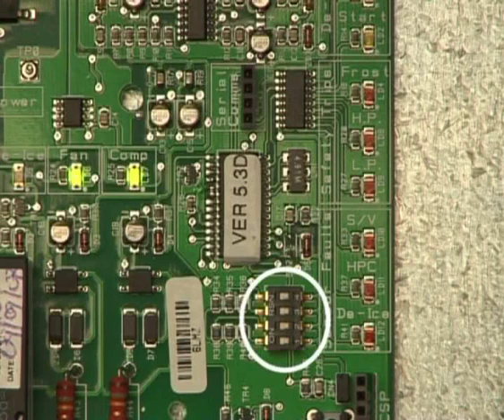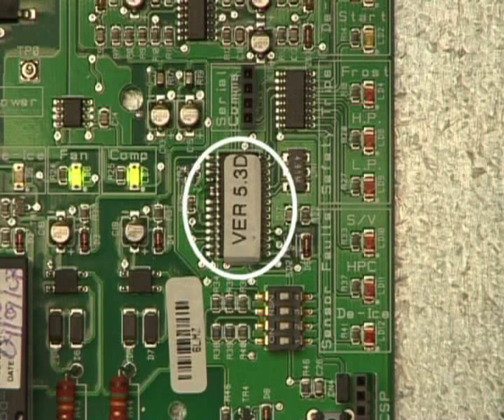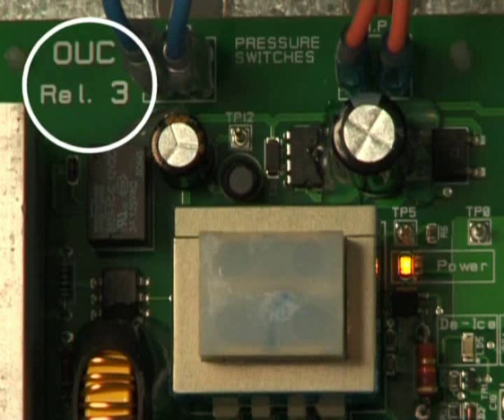The OUC has 4 dip switches. The dip switches are factory set in accordance with the product type that the OUC is fitted to. Detailed information on the dip switch settings can be found in the OUC Operation and Fault Diagnosis booklet, which has been included in today's information pack. Each OUC has its particular version program number affixed to the microchip, which is directly adjacent to the column of LEDs. There is also a release number which is located in the top left-hand corner of the OUC. This combined information will need to be supplied to technical support staff to aid in troubleshooting potential problems.